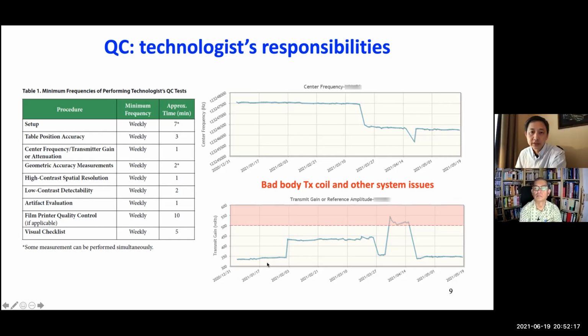Okay. In this case, initially we saw transmission gain increase. So that tells us the transmitter may have some issue. And then followed by center frequency drop. And then finally, it goes outside of our own baseline. So physicists need to establish a reasonable baseline. Usually we use about 3 standard deviations of the baseline measurement.